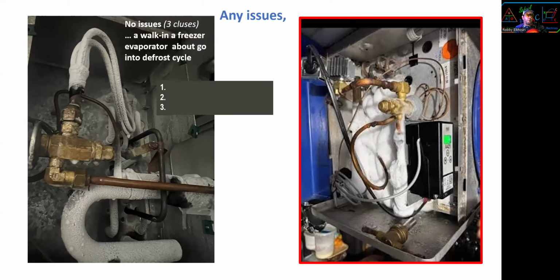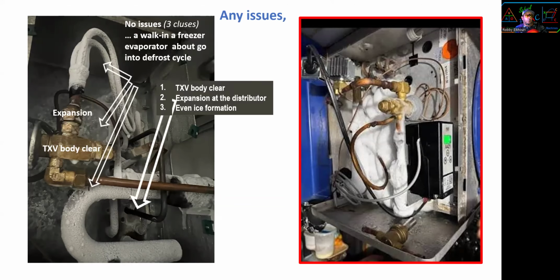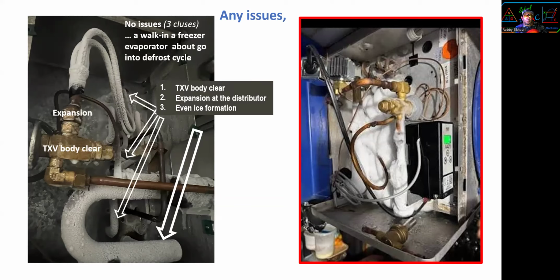A walk-in freezer evaporator about to go into defrost. I can tell so much just by visual inspection. Number 1, the TXV body is clear. Alrighty. Number 2, the expansion at the distributor. Expansion correct at the expansion line. And number 3, even ice formation everywhere. That will tell me it's about to go into defrost. Nothing's wrong with it.